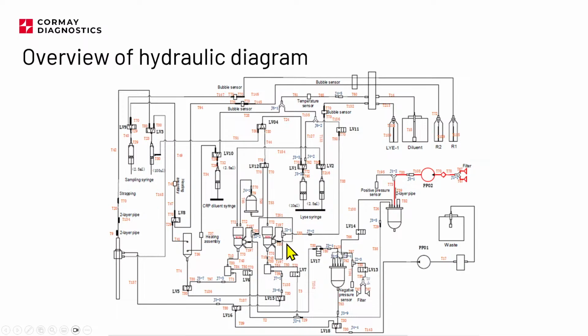So actually the device will use this valve, this chamber, and those connections to take liquid from here, pass it through the aperture, and make the measurements, right? This is quite simple. And this part of the circuit is connected to the diluent because we need to have a way to prime this part of the circuit. You don't want to have air on this side of the circuit. You want to prime this whole thing with a diluent, because you want to have diluent on one side of the aperture and also on the other side of the aperture. If you remember how the diagram or the split view of the aperture looks like, there were those two connections, and this was the port for the vacuum basically. So this is it. This is also part of the rinsing circuit for the aperture. This is quite simple, I hope at least.